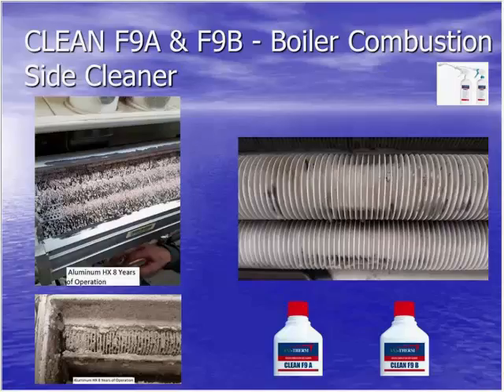Mm-hmm. This boiler was doing a building in a dog kennel. And so it was strictly floor heat, lots of condensing. This is after 8 years of operation. The guy actually had a service contract where somebody came to check it every year. He obviously didn't look in the dry side. And this is what happened this last fall when somebody finally opened it up because the boiler simply would not fire.